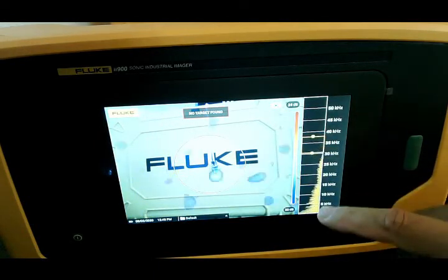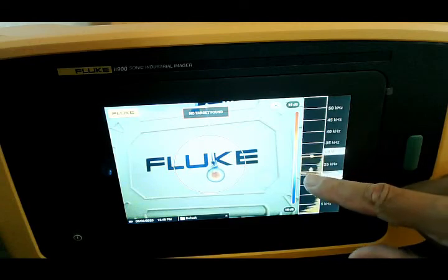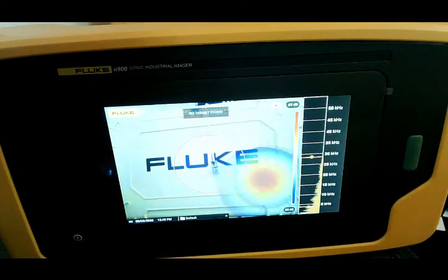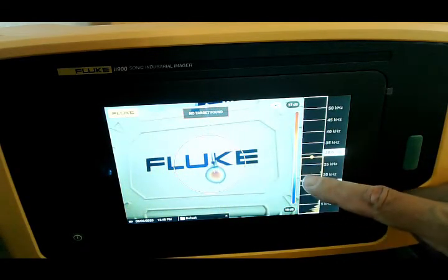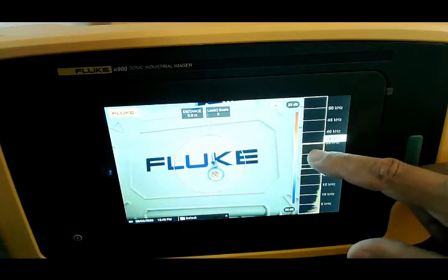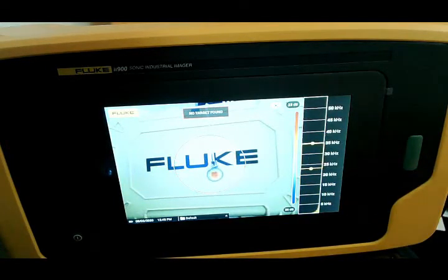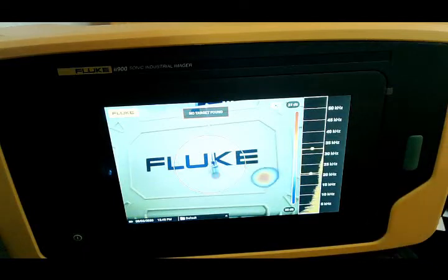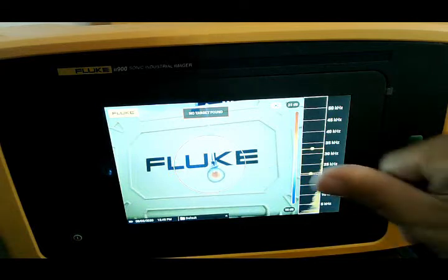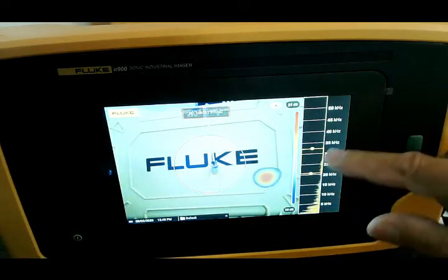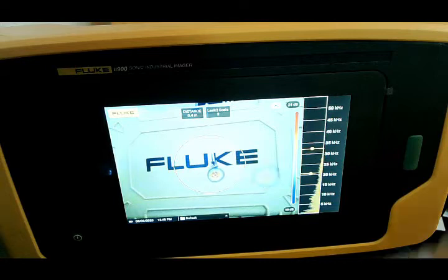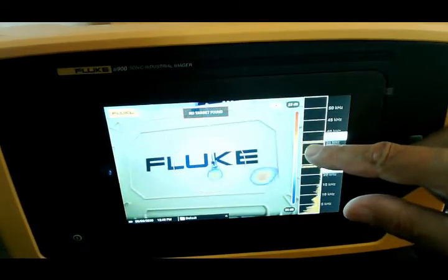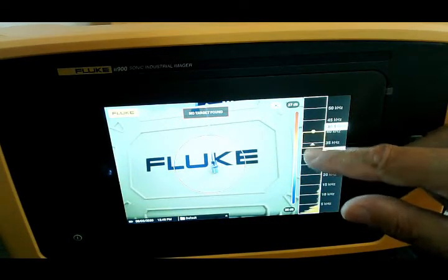We can do this by simply dragging it with a finger. We can widen the band to catch more noise, or narrow the band to catch just specific noises. This allows us to pinpoint exactly where we need to be. From my experience, I usually start between 20 and 35 kilohertz — about a thumb's width — and from there I can usually pinpoint most air leaks no problem. As I get closer to what I'm looking for, I narrow that band up.